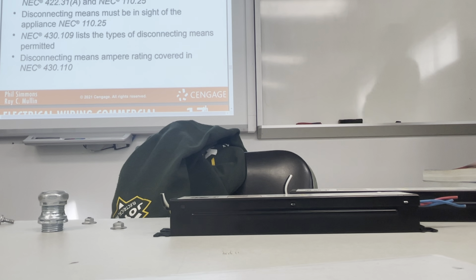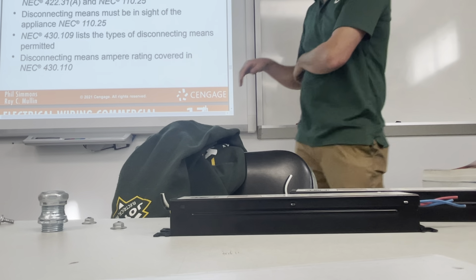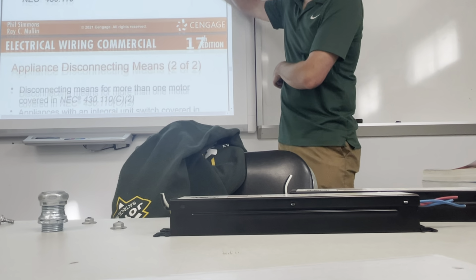Appliance disconnecting means required to be provided for each appliance. Permanently connected appliances are covered in NEC 422.31(A) and NEC 110.25. Disconnecting means must be in sight of the appliance. NEC 430.109 lists the types of disconnecting means permitted. Disconnecting means ampere rating is covered in NEC 430.110. And take this last slide.